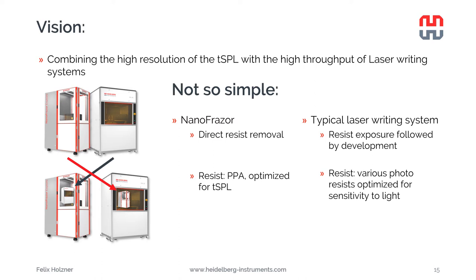This is not as simple as it might look. We cannot just put a small laser writing system inside the NanoFrazor, because the two technologies have quite different working principles. The NanoFrazor's heated tip directly removes the resist so no development is needed, whereas in a laser writing system you first expose the resist and only afterwards remove it with development. Also, the resist used in the NanoFrazor is PPA, which is optimized for thermal scanning probe lithography and is quite insensitive to light - it's basically transparent. The resists used in laser writing systems are highly sensitive to light, but if you try to push a heated tip into them, they make it quite dirty.